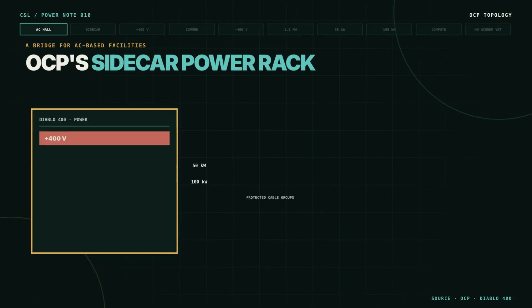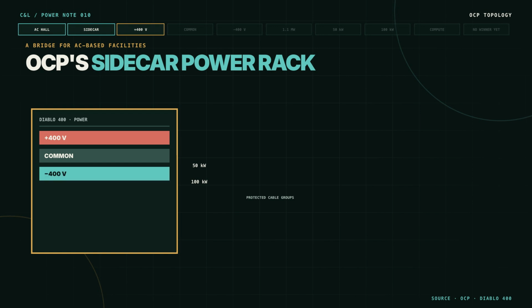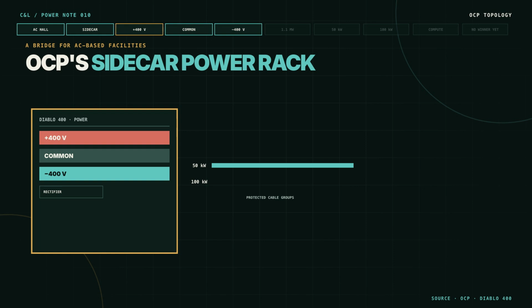Existing buildings create a transition problem. Their halls use alternating current distribution, while future racks may want high-voltage direct current. One bridge is a sidecar power rack beside the compute rack. Open compute documents reveal an important naming detail. Diablo 400 produces plus 400 volts, a midpoint, and minus 400 volts. That is 800 volts rail to rail, but it is a 3-conductor topology, not automatically the same as every 2-conductor proposal.